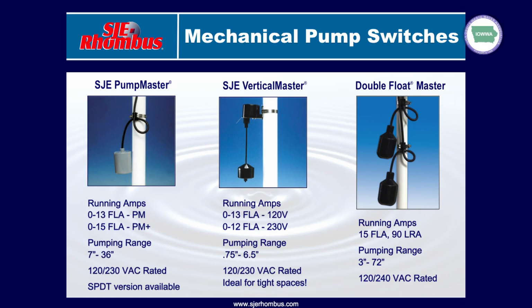for running your effluent pump or your sewage pump. And then we also build, and other manufacturers build as well, a double float with a holding relay in it. The double floats typically require that both floats be in the up position for the pump to come on. Both floats have to drop down and be in the off or down position for the pump to shut off. So you can have a much greater pumping range with a double float than you would get with a single float or a vertical float. Typically, we're going to go up to about 6 feet on the pumping range for the double floats.